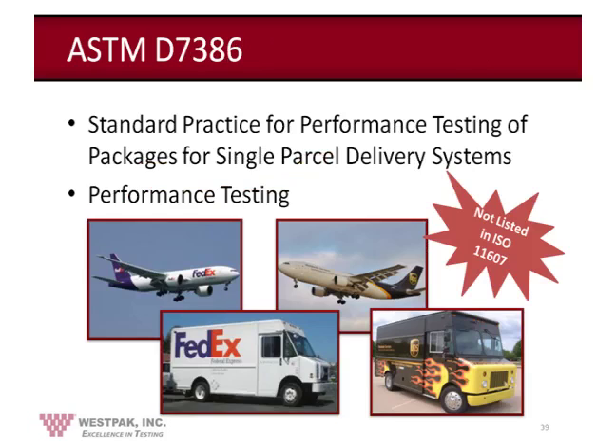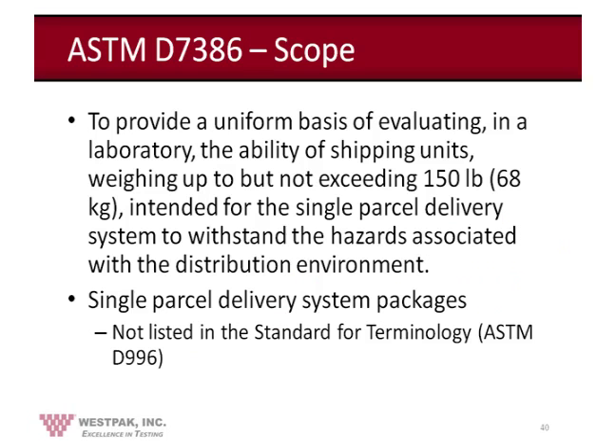ASTM D7386 is a standard practice for performance testing of packages for single parcel delivery systems. According to the standard it is performance testing, but we define it as integrity testing because it's a qualitative rather than quantitative test. The standard is not currently listed in ISO 11607 because the latest revision of ISO 11607 is from 2006. The scope of ASTM D7386 is to evaluate the ability of shipping units to withstand hazards associated with a single parcel delivery system environment. A single parcel delivery system is a distribution courier that transports packages weighing up to 150 pounds through ground and/or air transport systems.